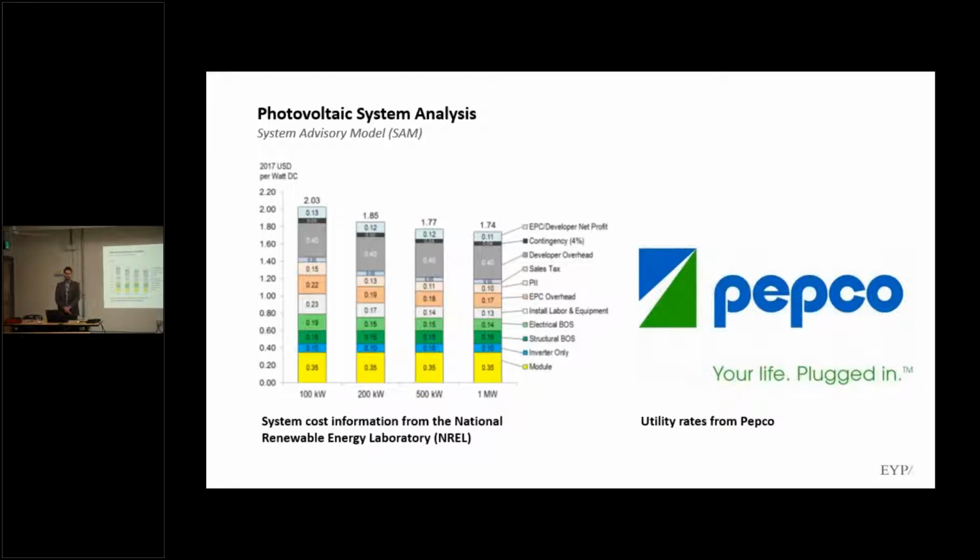In terms of energy production, it's pretty spot on. Over the course of a year, there are a lot of studies that have looked at what our weather files show versus our actual local solar radiation availability, and they're quite close if you average them out. So the actual generation potential is quite good, and the System Advisor Model is very powerful because it takes into account degradation over time: the inverters and the panels becoming less efficient, needing to replace the inverters every 10 years or a certain life cycle. So it takes those considerations into account when doing the cost assessment. So it's pretty accurate at the end of the day.